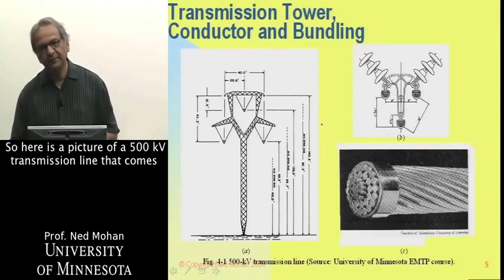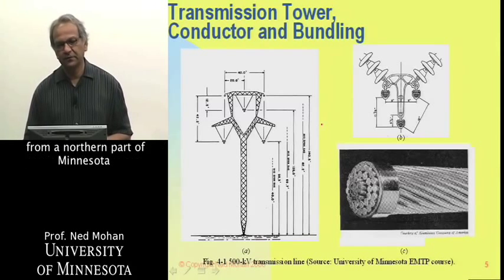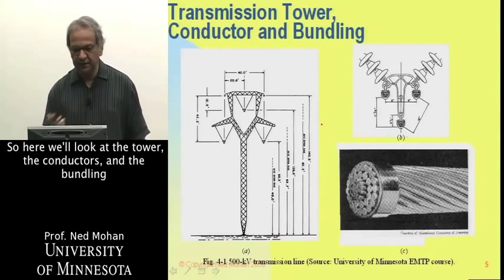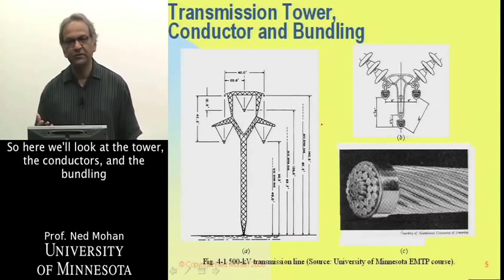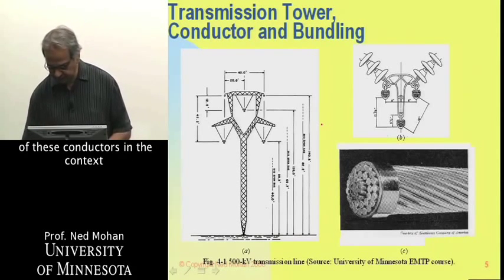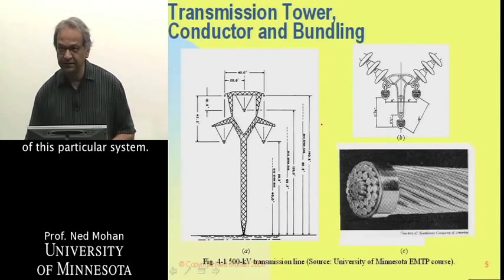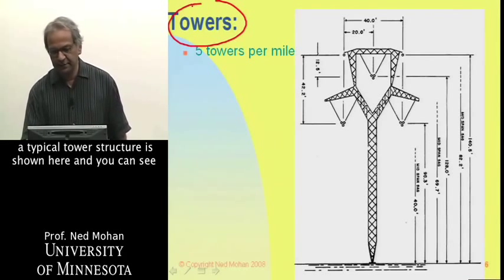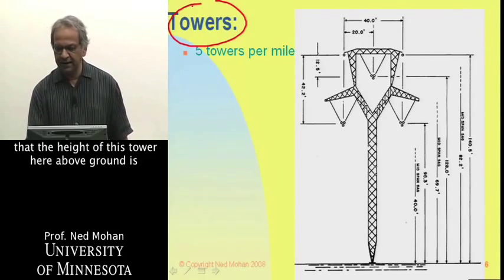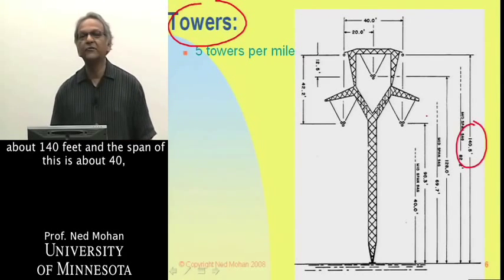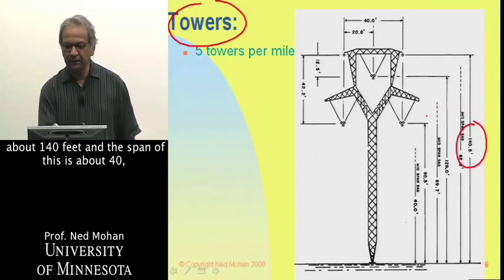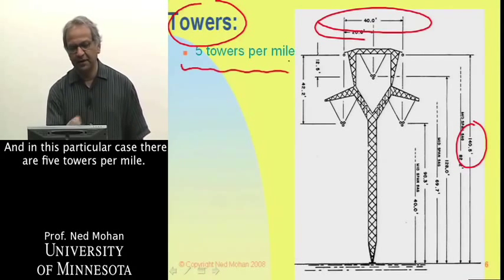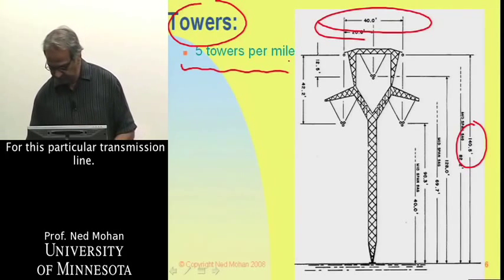Here is a picture of a 500 kV transmission line that runs from the northern part of Minnesota to somewhere very close to the Twin Cities. We look at the tower, the conductors, and the bundling of these conductors. A typical tower structure shows that the height above ground is about 140 feet, and the span is about 40 to 50 feet, with five towers per mile for this particular transmission line.